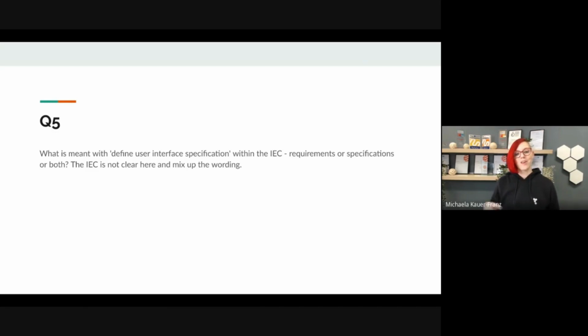And combining that with the argumentation that because they are testable, like I can measure the size of my button, that they can only do verification instead of a validation, so they don't need any usability engineering studies. As you can imagine, I find that a very interesting argumentation, and it did work some years ago. It's not working anymore.